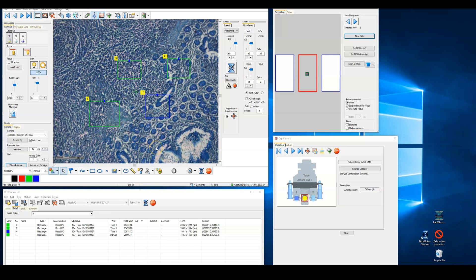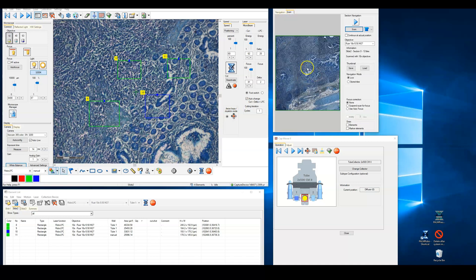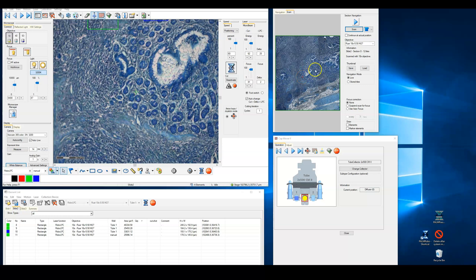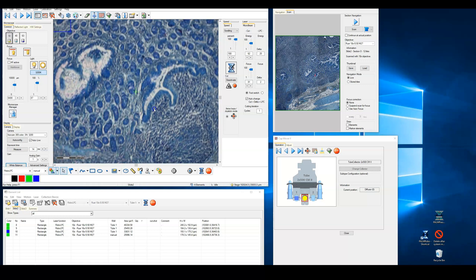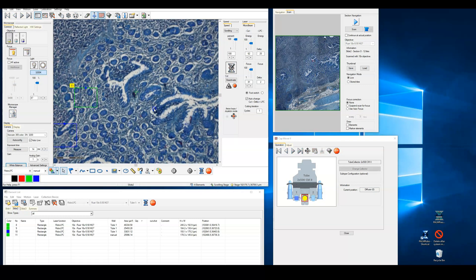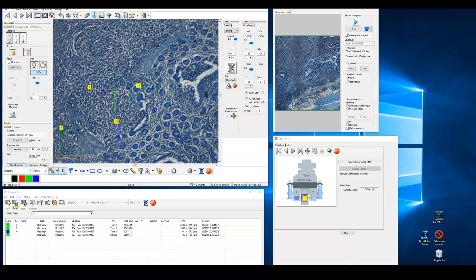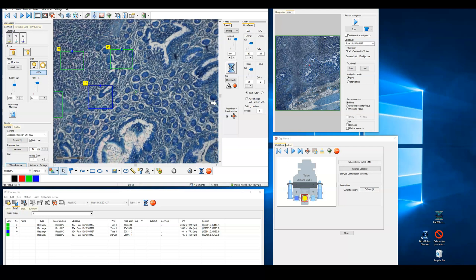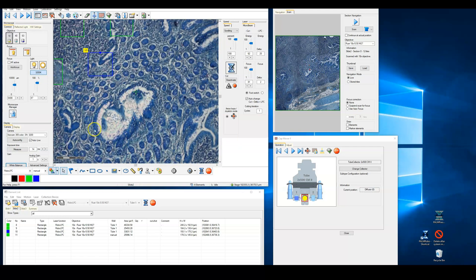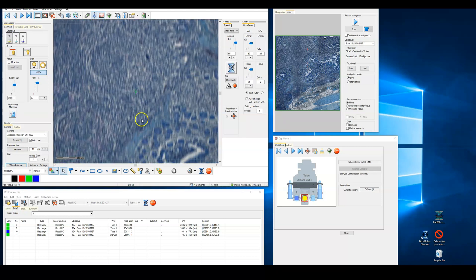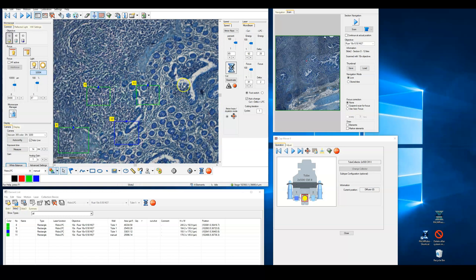There are a number of ways to navigate on the sample. We've already seen that we can navigate in a very fast manner by clicking on a region of the slide in the navigation window. There are three additional ways to move the stage. We can use the joystick, which provides a sort of intermediate speed of travel. We can click on the border of the live window, which provides a single fast jump in one direction. And we can use the arrow keys on the keyboard. This provides the finest control over the stage movement. The speeds of each of these mechanisms of movement can be controlled by the right hand side of the live window in this section labeled speed. Here we can also see that we can customize the cut speed.